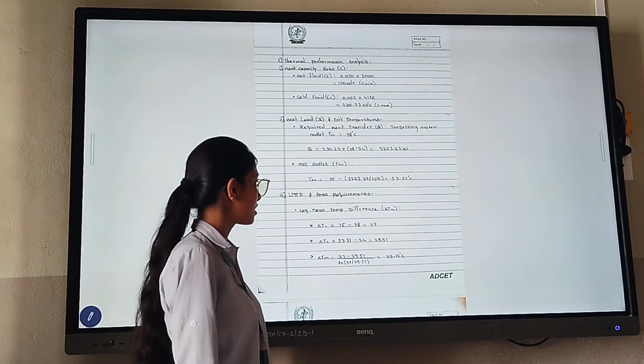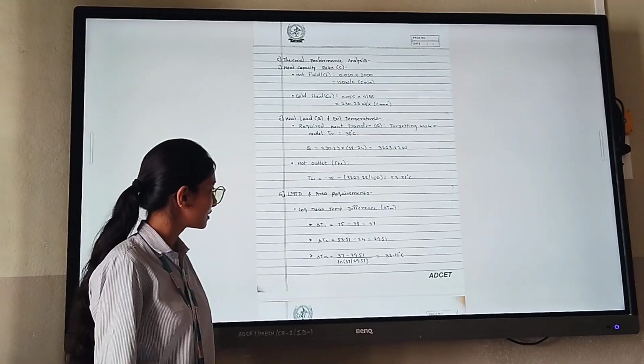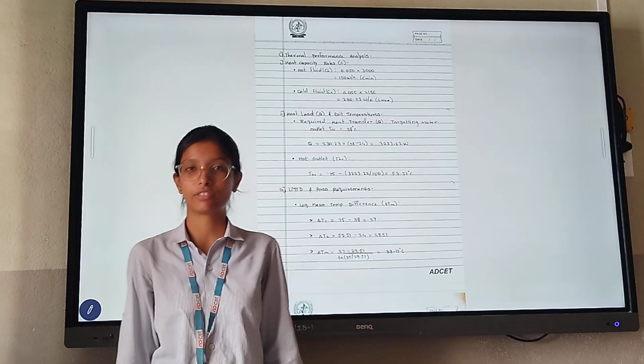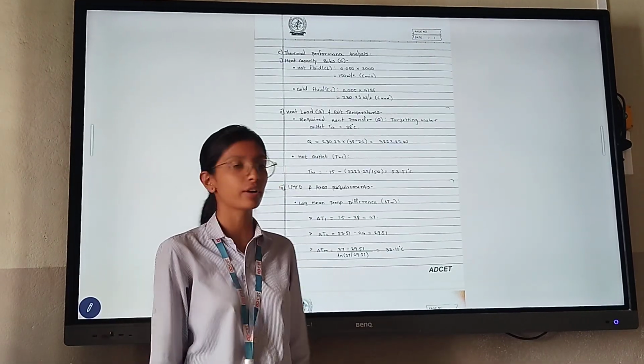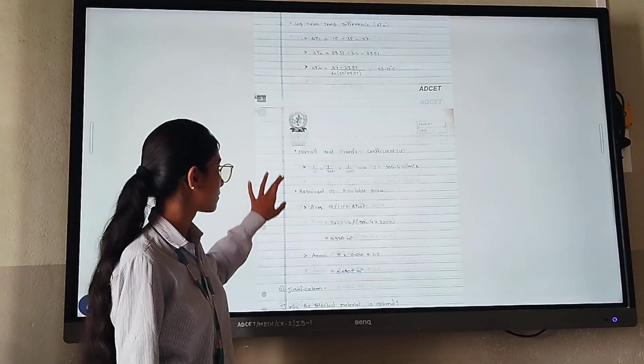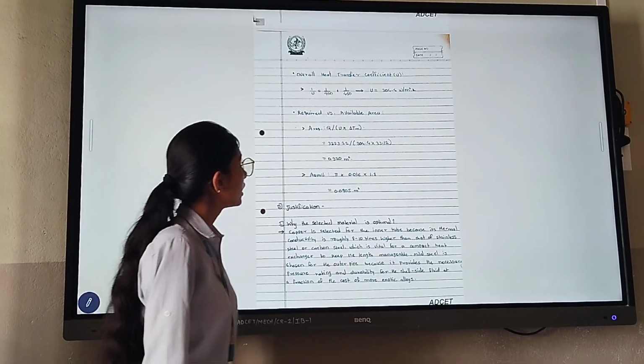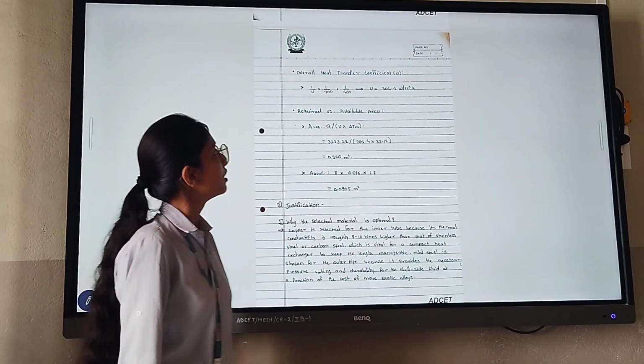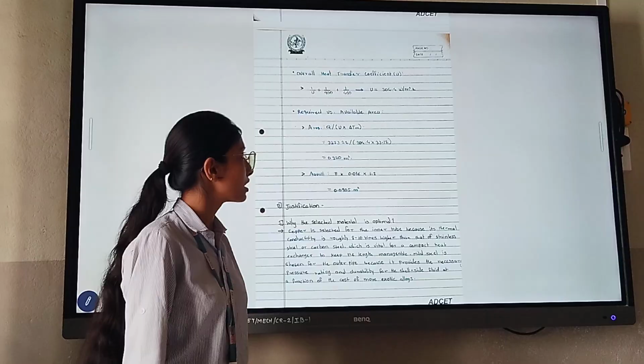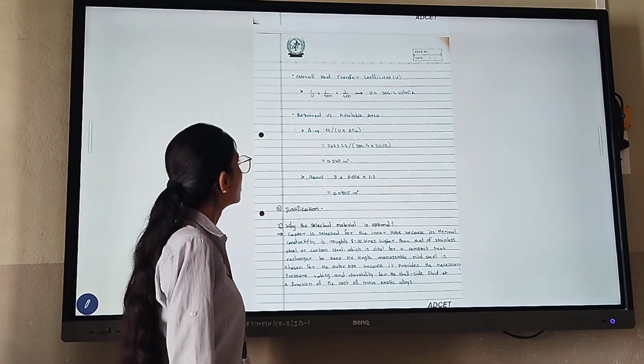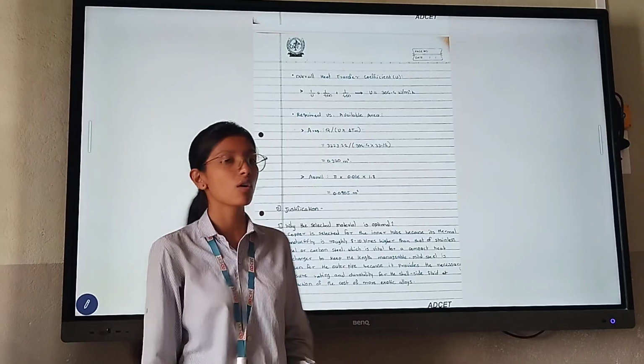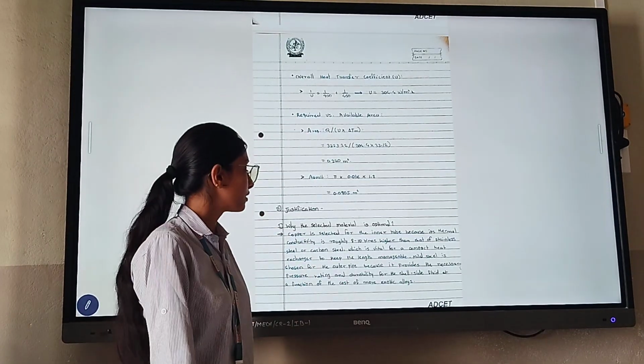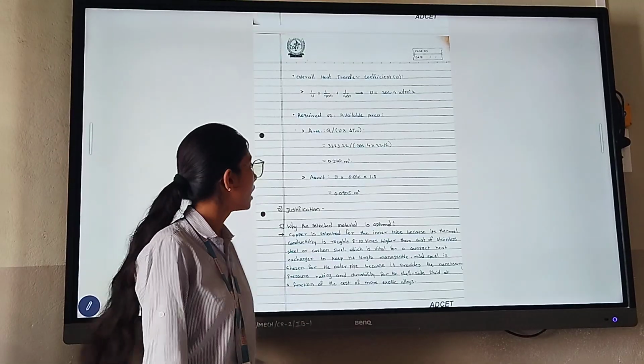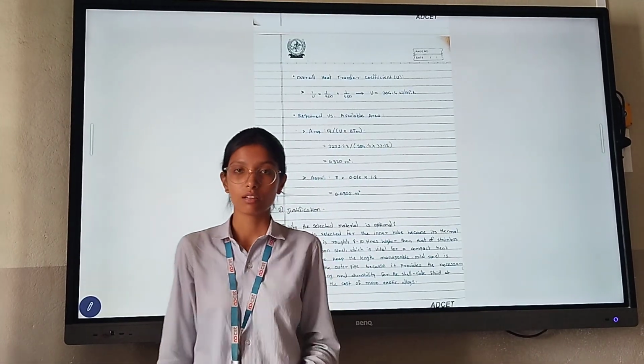Then LMTD and area requirement. Log mean temperature difference: delta T1 equals 37, delta T2 equals 29.51, and delta Tm equals 33.12 degrees Celsius. Overall heat transfer coefficient calculated equals 304.4 watt per meter square Kelvin. Required versus available area. Required area is 0.320 meter square and available area 0.0905 meter square.